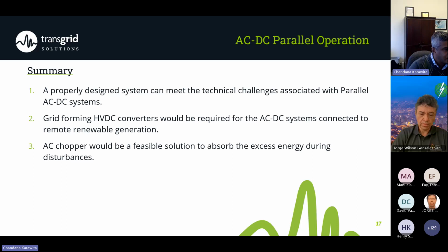And then you need to include the frequency dependent characteristics of both the AC and DC lines. Basically, create the reduced system with the HVDC embedded and do the simulation in EMT and evaluate the coupling. So this should be done in EMT, and I showed some of the results during the presentation. They were all done in EMT software.